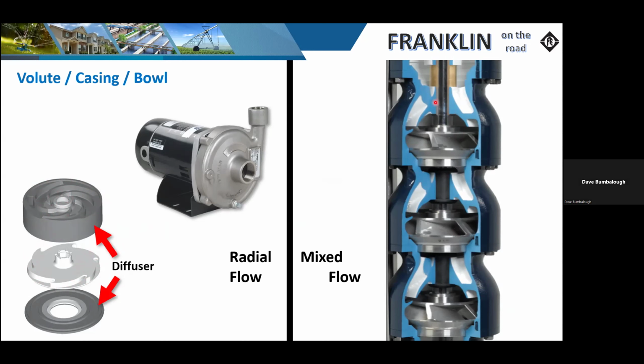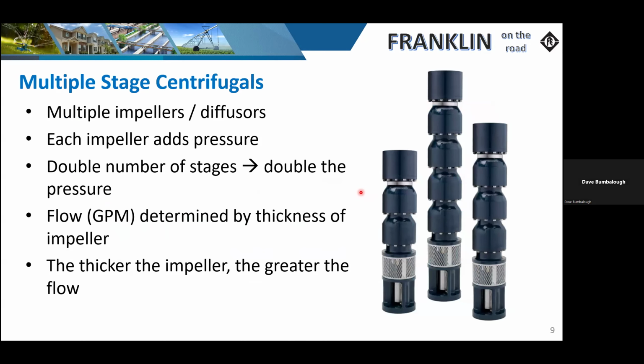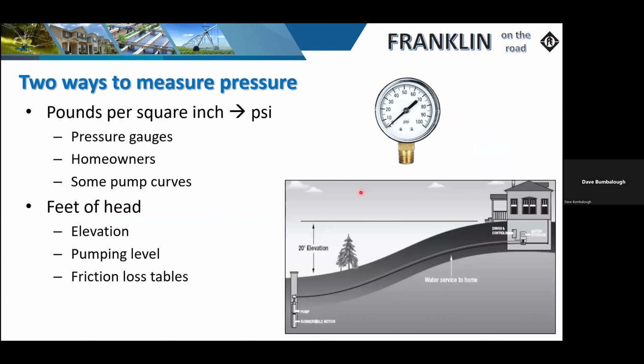So when we put multiple stages together, ultimately what we're trying to achieve is to build up pressure. These are typically going to be set in a deeper application. We're having to lift that water to the surface, which may be some distance down in the well. And then plus, we've got to be able to build up pressure for the application that it's involved in. So now that we're on the subject of pressure, there's two ways of measuring pressure. We can do it either in pounds per square inch, or we can do it in feet of head, which both are crucial for our calculations and sizing and determining what the system is doing.